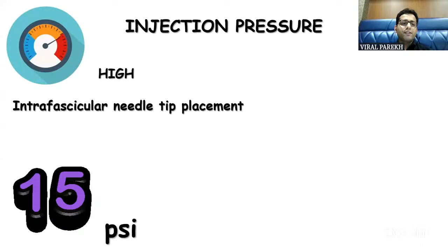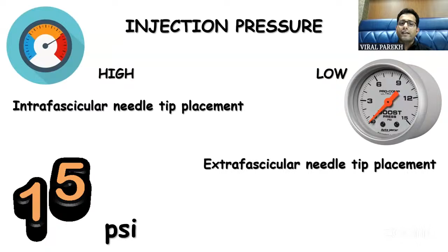So coming to the injection pressure monitoring, as I already described, if the needle is intrafascicular, the injection pressure will be high, and if the needle is extrafascicular, the injection pressure would be low. And this cutoff has been revised by various studies to about 15 psi. So if the injection pressure is more than 15, there could be a possibility of intrafascicular needle tip placement.